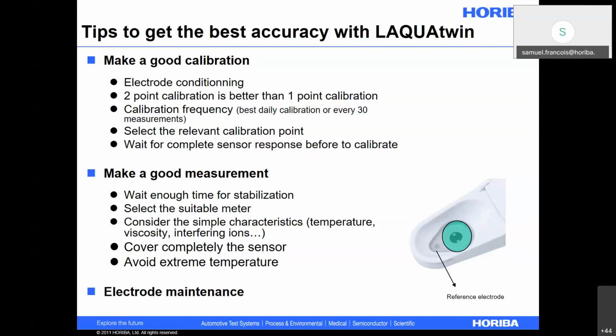So fortunately, on the LAQUAtwin meter, we can adjust the two calibration points to make sure that we fit the concentration of our sample. Okay? And also, this is very important to wait for the complete sensor response before we calibrate. So on the meter, there is a calibration button, and I always recommend to our customers first to put the calibration solution on the sensor, wait to see that the reading is stable and doesn't move anymore, and then after that we can calibrate. Otherwise, sometimes the meter tends to calibrate too quickly, and then we don't have the perfect calibration.